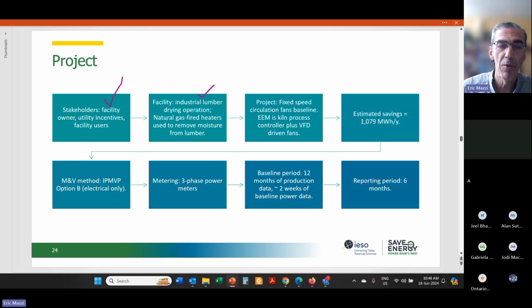So it was a lumber drying operation. It was natural gas fired heaters in this lumber drying kiln. The baseline was fixed speed. The energy efficiency measure was a new controller plus VFDs to drive the circulation fans. And it was VFD on the burner fan as well. Again, not necessarily real numbers here because I've altered things, but the savings were around 1 million kilowatt hours per year estimated pre-project. We went with retrofit isolation, IPMVP.